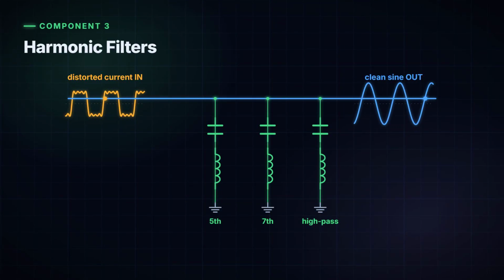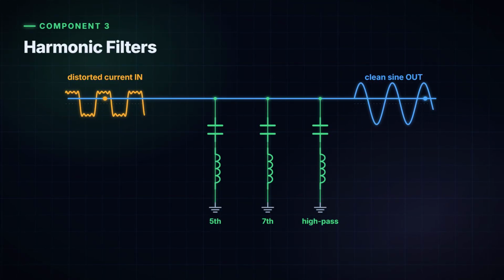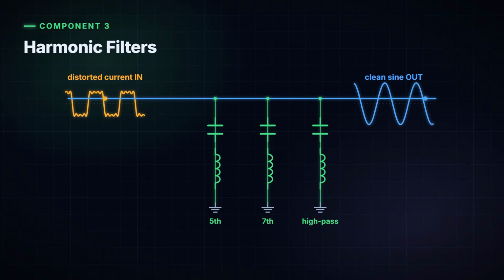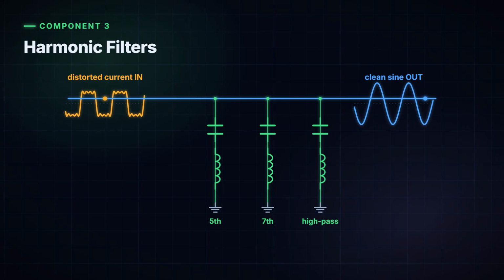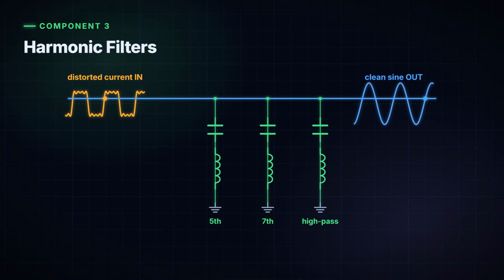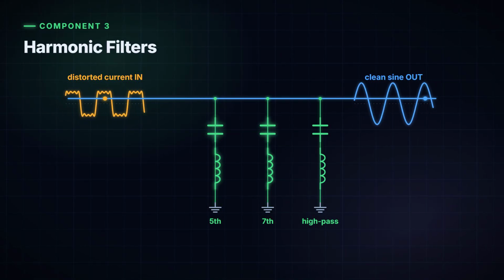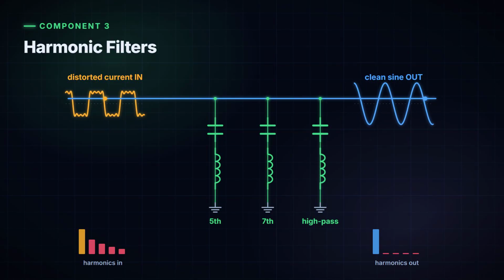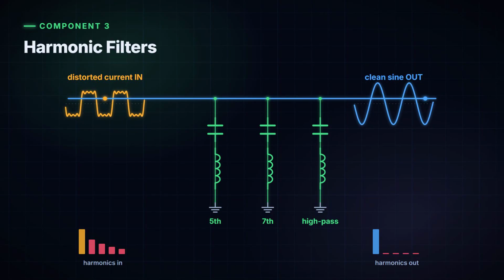Remember that distortion the TCR created? This is where we clean it up. These are harmonic filters, tuned combinations of inductors and capacitors, each one designed to provide a low resistance path for a specific unwanted harmonic, draining it away before it reaches the grid.